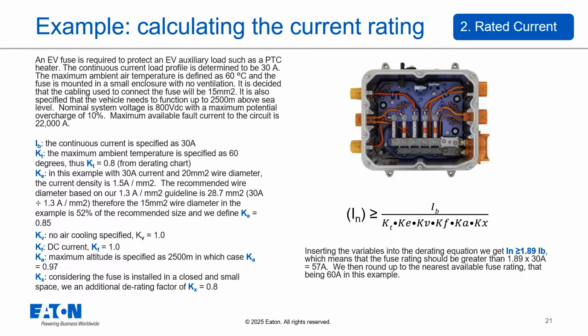K sub T for 60 degrees C is 0.8. For K sub E, the thermal connection derating factor, the example calculates current density based on the 15 millimeter squared wire and 30 amps. The recommended guideline is 1.3 amps per millimeter squared. Based on this calculation, the 15 millimeter square wire is about 52% of the recommended size, leading to a K sub E of 0.85 in this example.